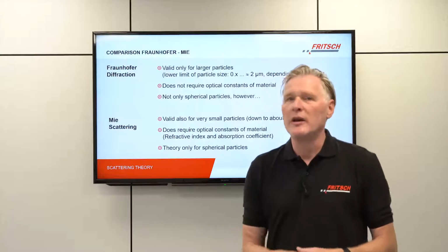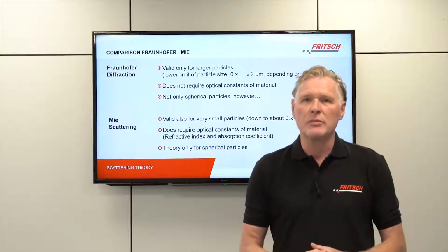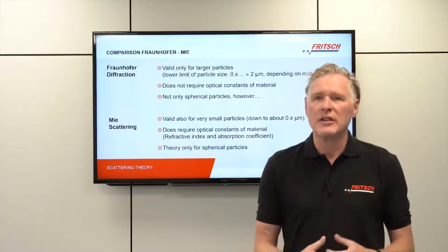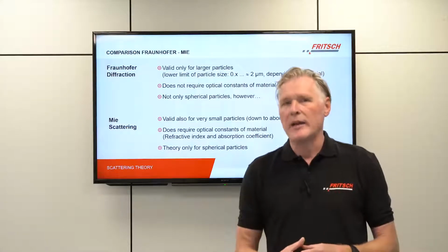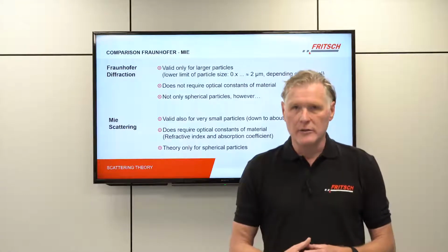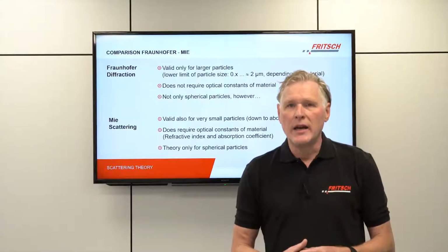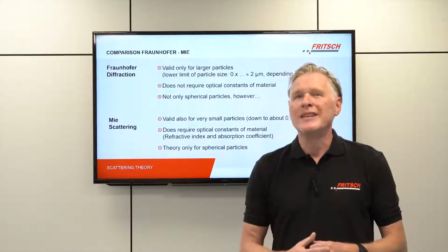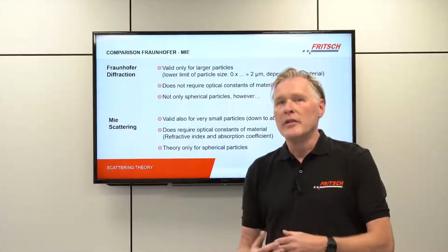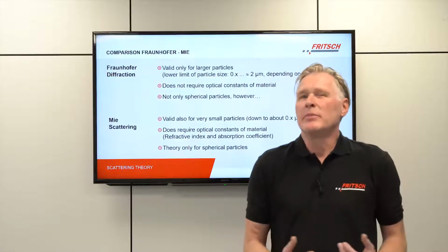In the software of our instrument, you find a database that contains around 2,000 different materials, but often you will have some new materials, some mixtures of materials, and so on. So that often makes it pretty challenging to get correct values. Some people may tell you that with this technique or with their instrument, you can determine the refractive index from the particle size measurement, but that's simply not really true.